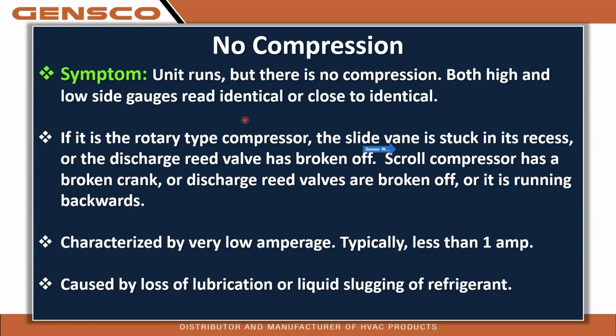It's characterized by very low amperage. In the case of a stuck slide vane in a dual rotary compressor, the amp draw while it is spinning will be less than 1 amp. And it's the way you can tell the difference between a stuck slide vane in a compressor causing no compression or a stuck reversing valve being halfway. It'll also cause no compression, but you're still moving refrigerant through the compressor, and the amp draw will be somewhat normal in that case. Now, this is caused by a loss of lubrication or liquid slugging of the compressor, causing damage.